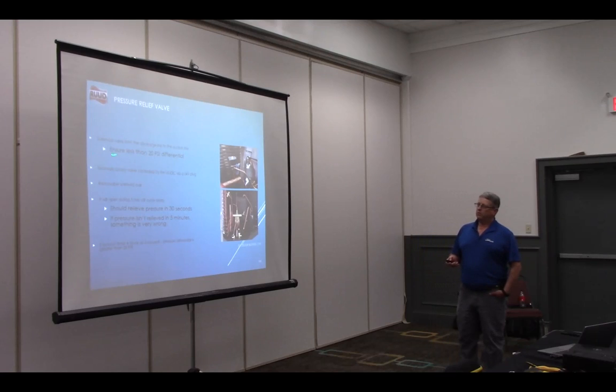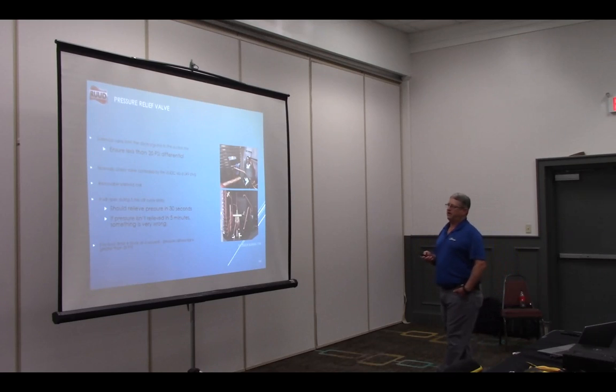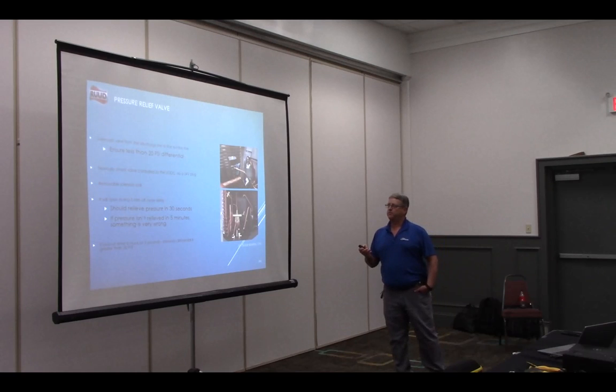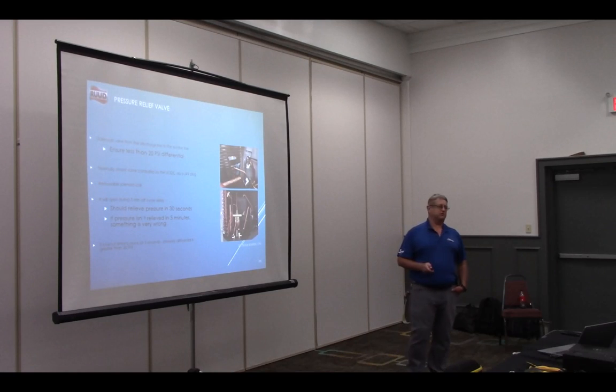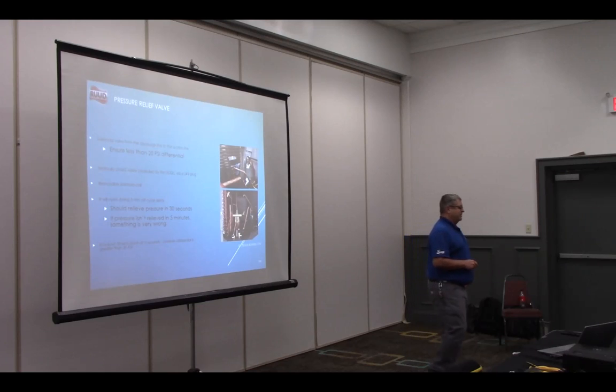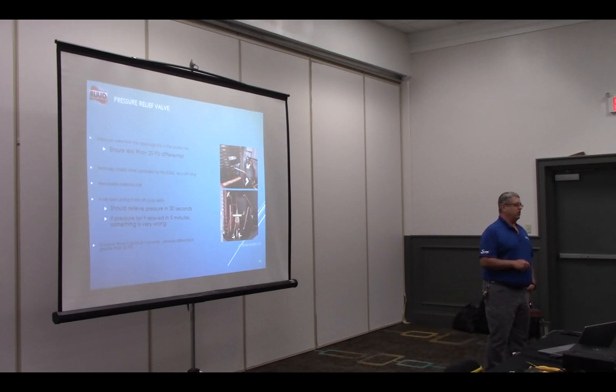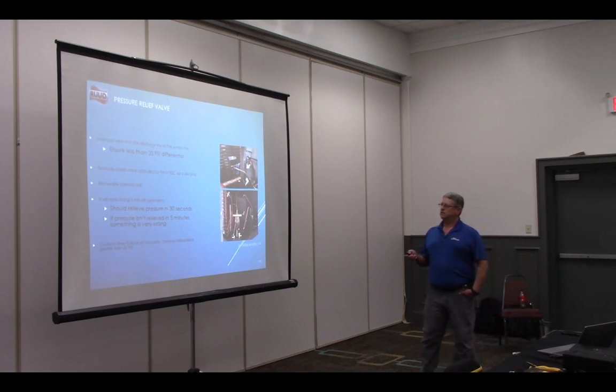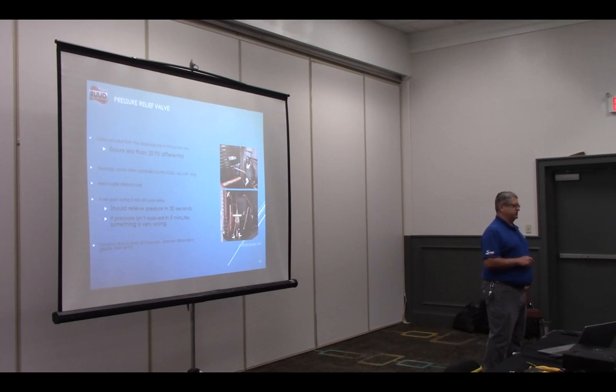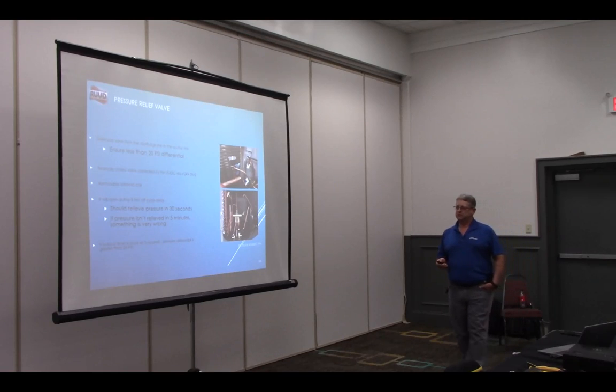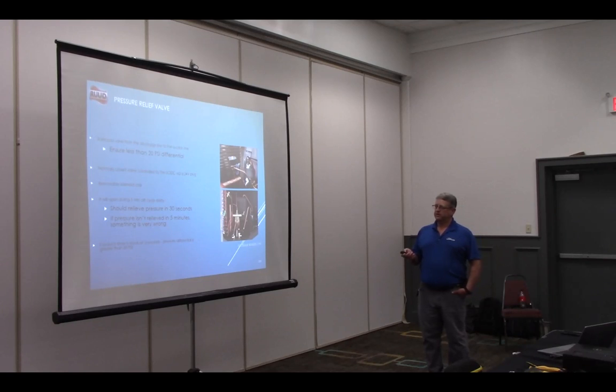We've got to ensure this is that pressure relief valve that we talked about. Less than 20 psi difference between suction and discharge. If it doesn't see it after that 5-minute off delay, it will open that valve to equalize the pressure. If you still have a greater than 20 psi difference, you have a restriction somewhere. You need to start looking at restrictions. Outdoor tubing we've talked about is going to be 7mm tubing outside.